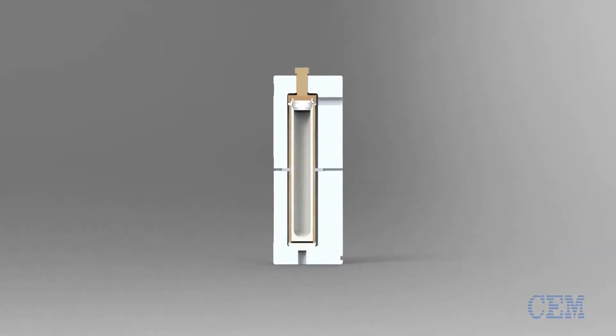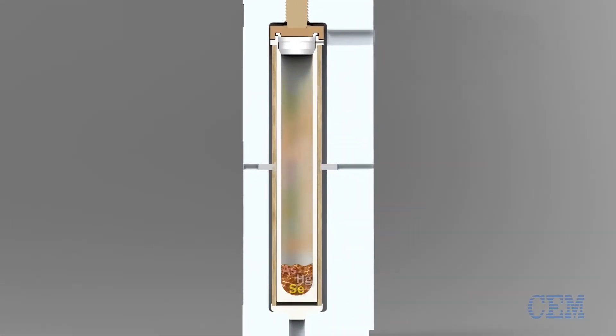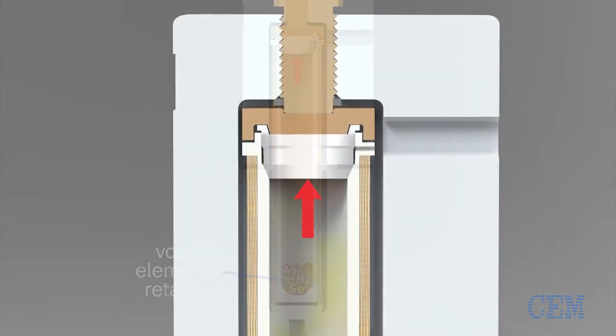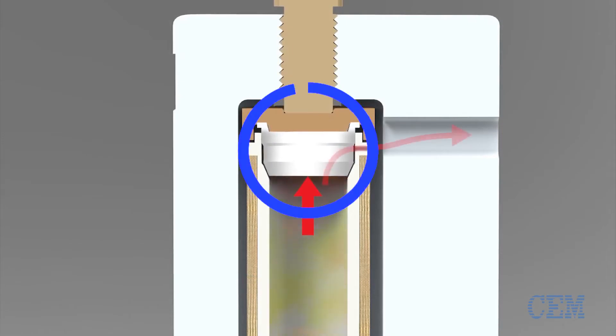The dual seal function also provides unmatched control of by-products from digestions such as CO2 and NOx fumes. I-PREP precisely vents these gases out of the vessel while maintaining the full integrity of the sample and analytes including volatile elements such as arsenic, selenium and mercury. The patented design of the dual seal plug provides a level of control and safety unmatched by other vent and reseal systems.